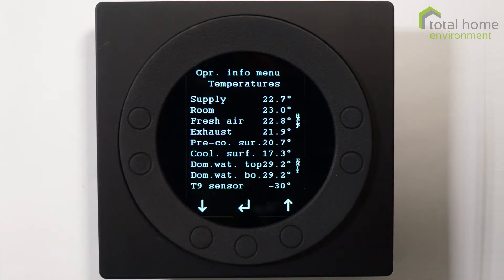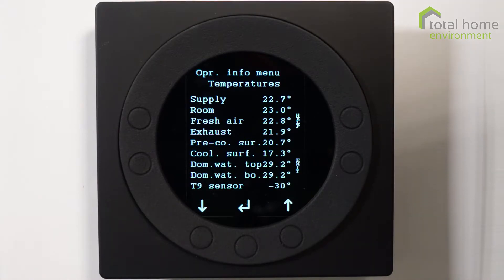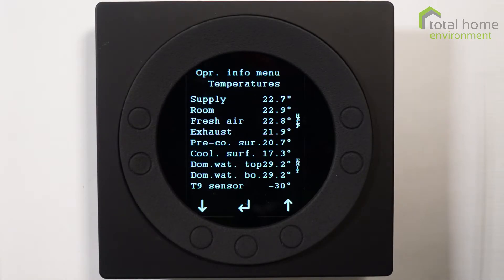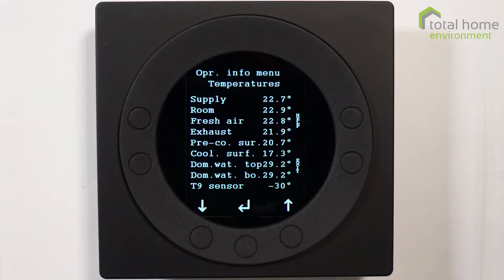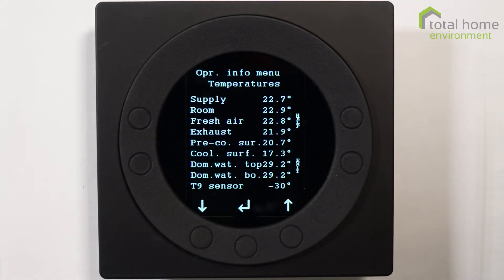Cooling surface is the temperature of the evaporator coil, and normally that would be much colder than that. Currently this machine is in a display mode so it's not actually doing any real work, which is why the top and bottom of the tank are exactly the same temperature. Below that you'll see T9 sensor and next to it is minus 30. Whenever you see a minus 30 temperature it means there is no sensor connected to that port. T9 is for additional sensing, for additional heating or for whatever purpose you might have - there are lots of reasons why you can put in an additional sensor and currently that's not connected to anything.